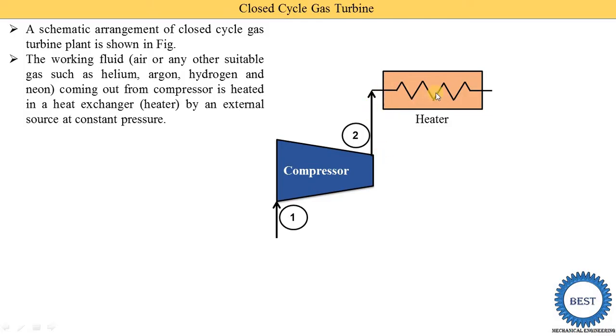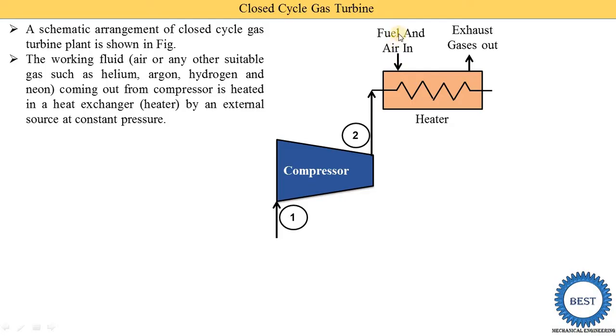This process is carried out at constant pressure in the heater — the working fluid is heated at constant pressure. Any process in the heat exchanger is considered as isobaric, meaning constant pressure. For supplying heat energy to the working fluid, fuel and air are supplied here and combustion is carried out. The combustion product is passed outside the tubes, the temperature of the working fluid is increased, and the exhaust gas from the heater is supplied to the atmosphere or used for some other process heating.